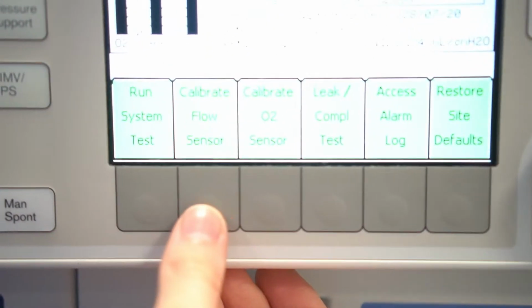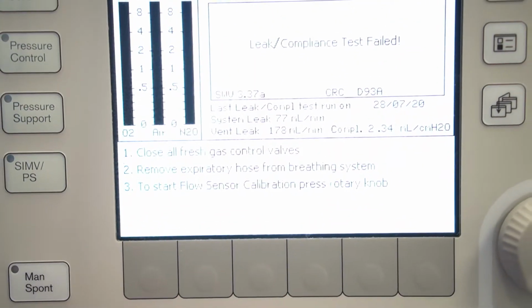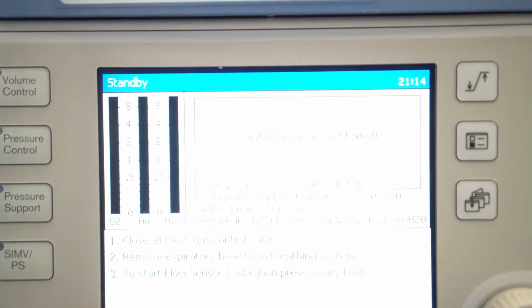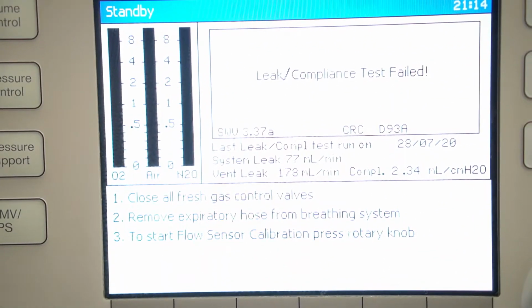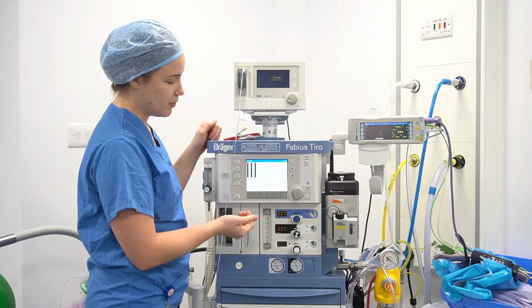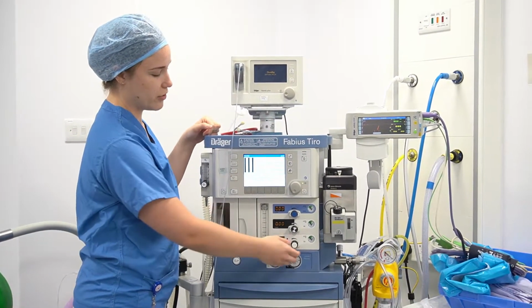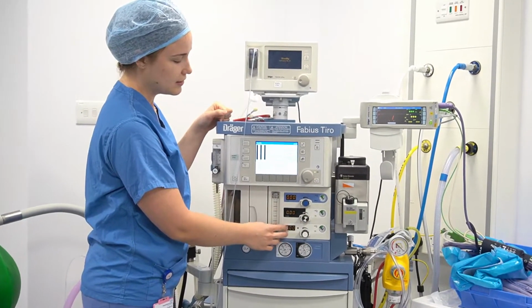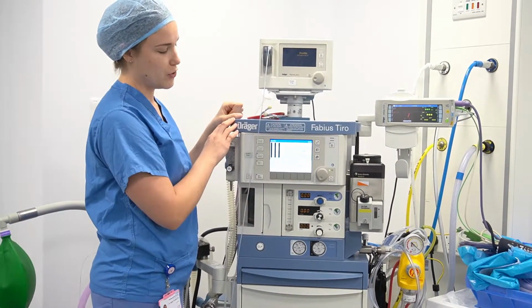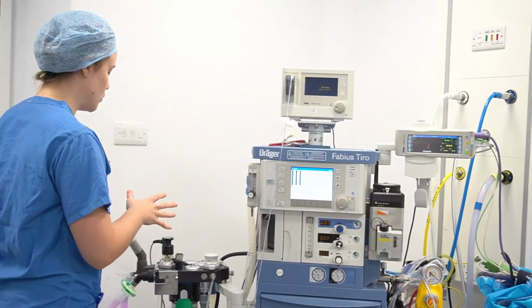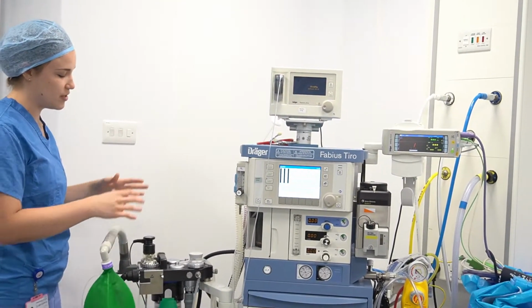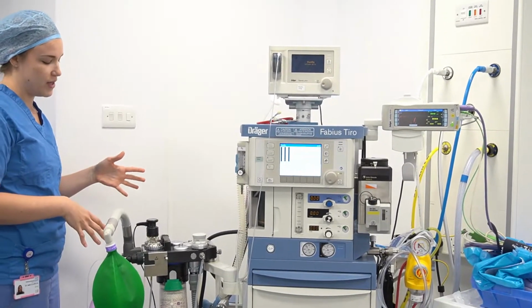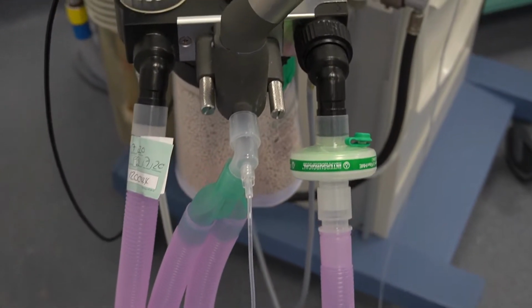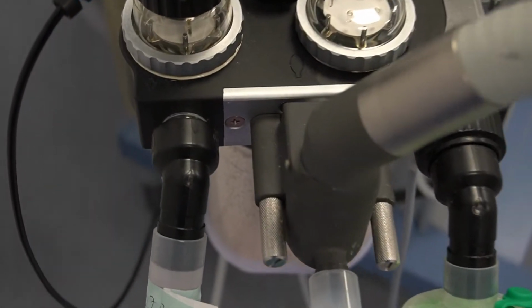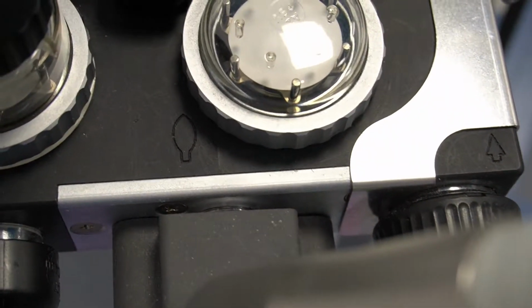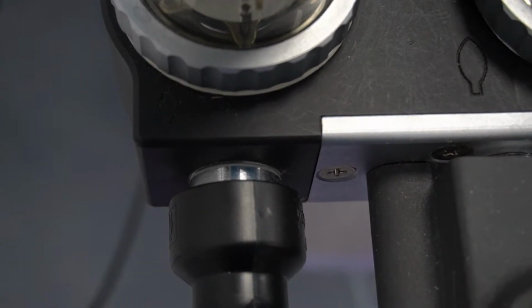So that will be for your flow sensors. So again, push the button, and then some of the tests will give you a list of instructions in order for the machine to complete the test. So this, for example, is going to ask us to close all the fresh gas valves, which we can see here, and then to remove the expiratory hose from the breathing system. So we then need to move on to this side of the machine, to the breathing system itself. If we have a look over here, the breathing system has got its expiratory limb and inspiratory limb. You can see the various arrows going towards and then away from the machine itself for expiratory and inspiratory respectively.